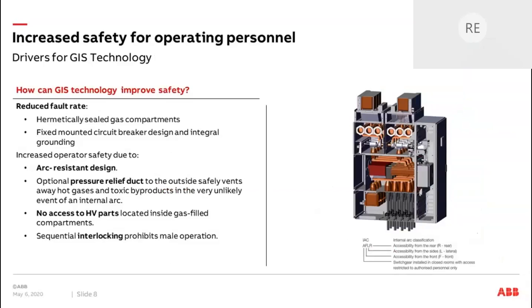Well, first of all, because on the right side you can see a GIS feeder panel, where you see 3 gas compartments. You see the 2 gas-filled busbar compartments on top, and in the middle, the gas-filled circuit breaker compartment. The high voltage parts, so the busbars, the 3-position disconnectors, and the circuit breakers are all located inside those gas compartments. So they are protected from environmental influence, which means the fault rate is drastically reduced. Furthermore, most faults happen during the operator working on the switchgear and not during normal operation. So for example, for maintenance or for repair reasons.